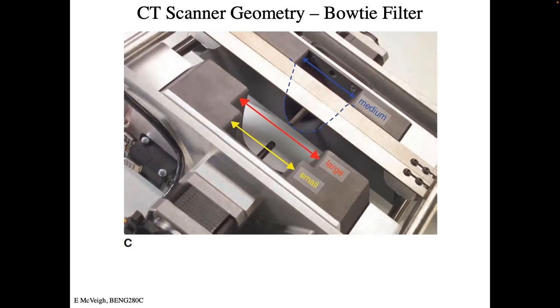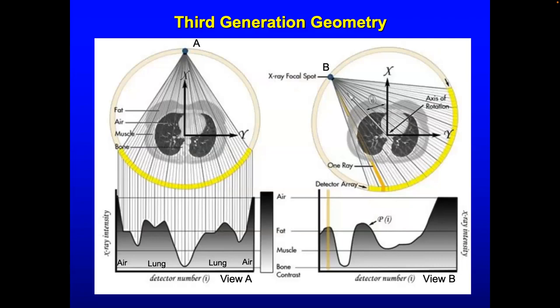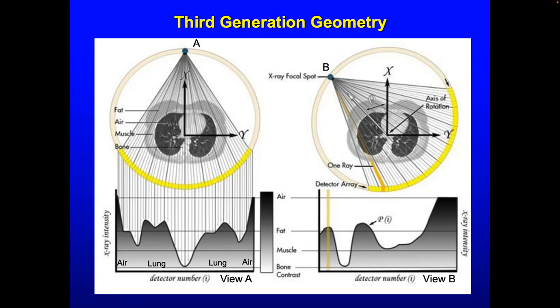The basic raw signal is parameterized by detector position i along the detector arc. For any 2D image, a projection is taken at one angle, then both source and detector rotate to a new angle for the next projection — repeated about 1000 times, roughly matching the number of detector elements in the fan direction.